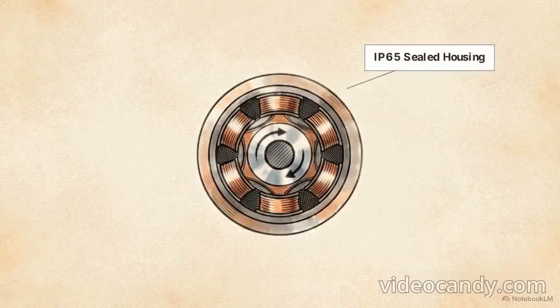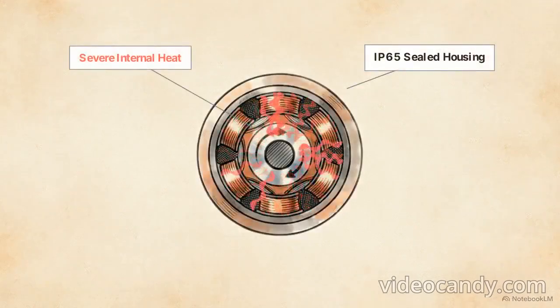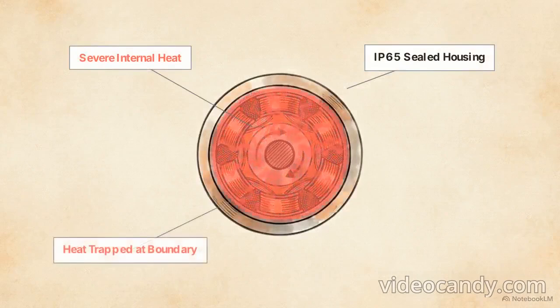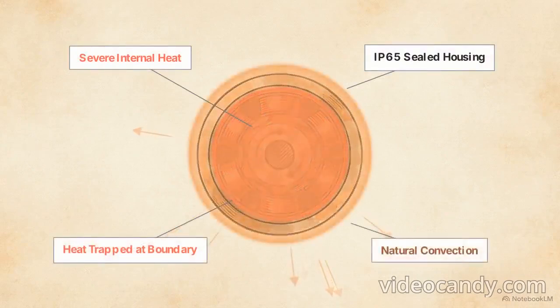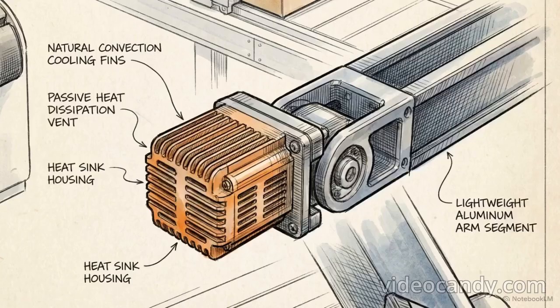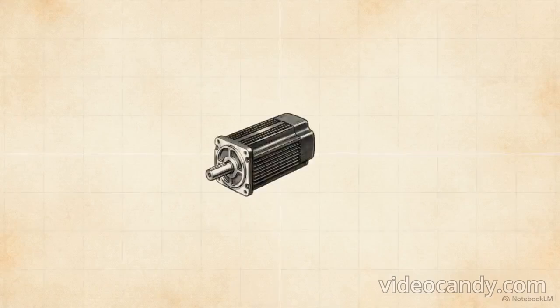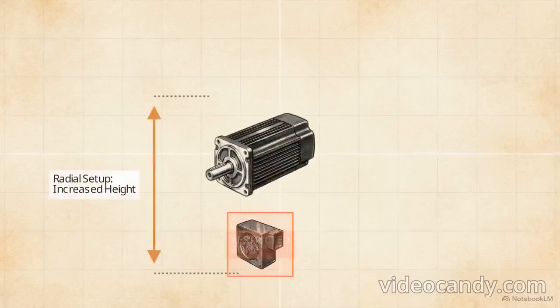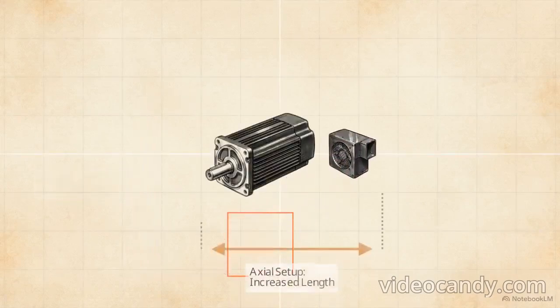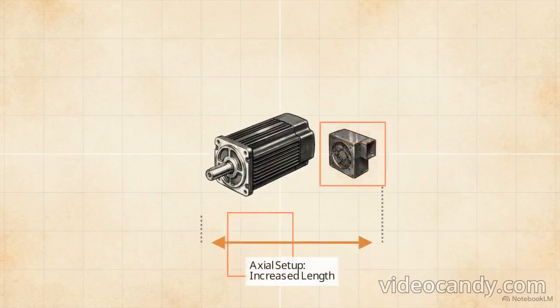Sealing the motors so tightly creates an immediate engineering hurdle. Continuous start-stop operations generate severe internal heat, and that heat has no direct path to the ambient air. The baseline cooling state for these motors is natural convection, where heat radiates out from the casing into the surrounding air. Natural convection is only sufficient for standard low-intensity duty cycles. Extreme repetitive loads dictate the use of active surface cooling blowers.